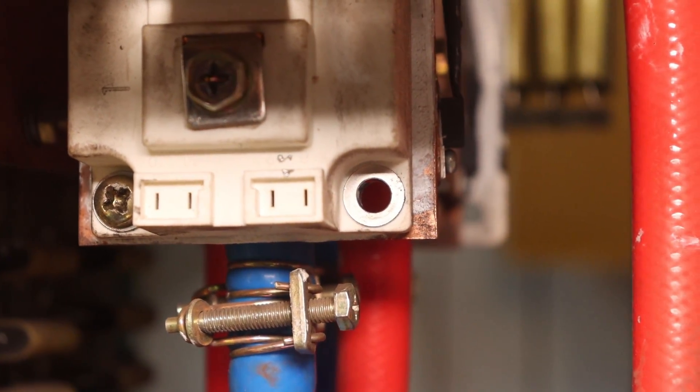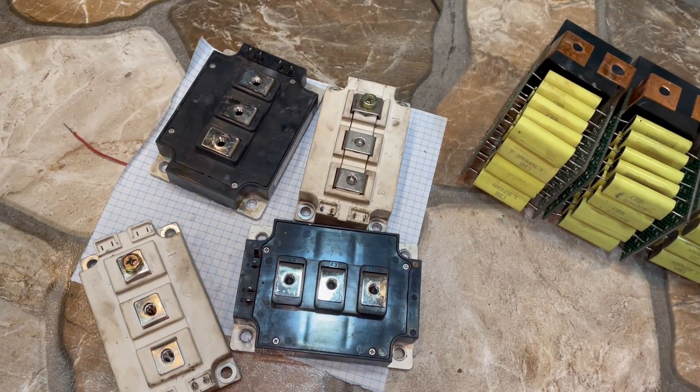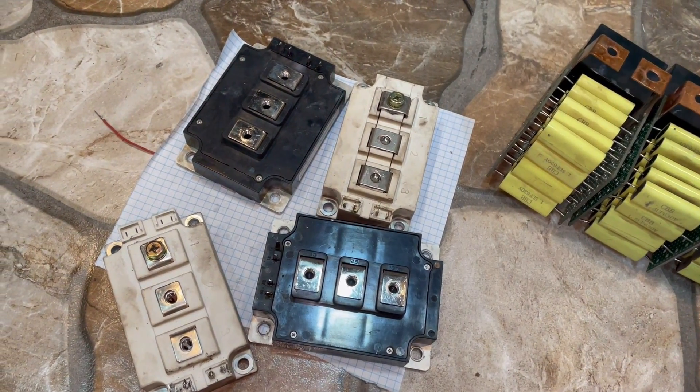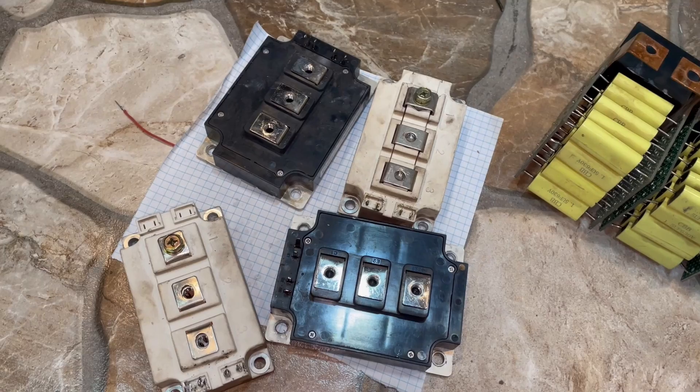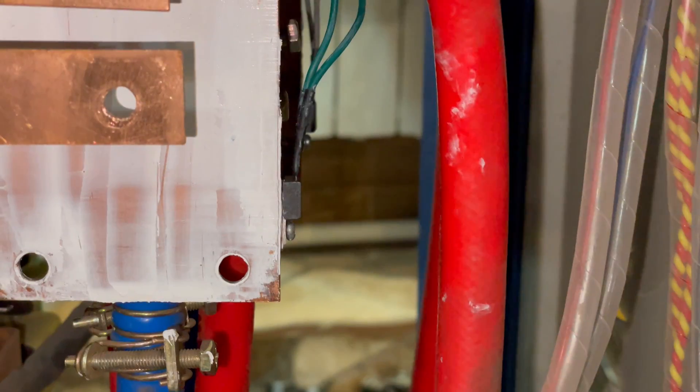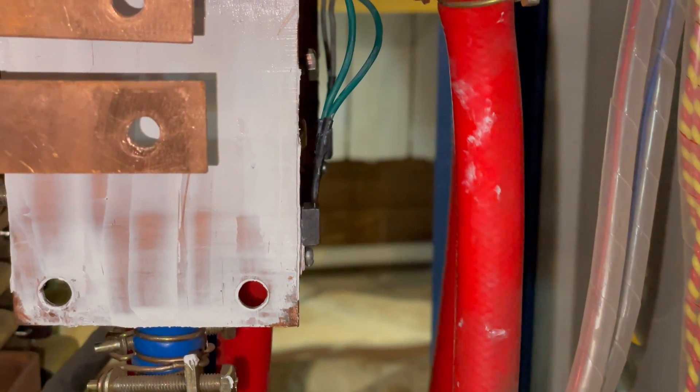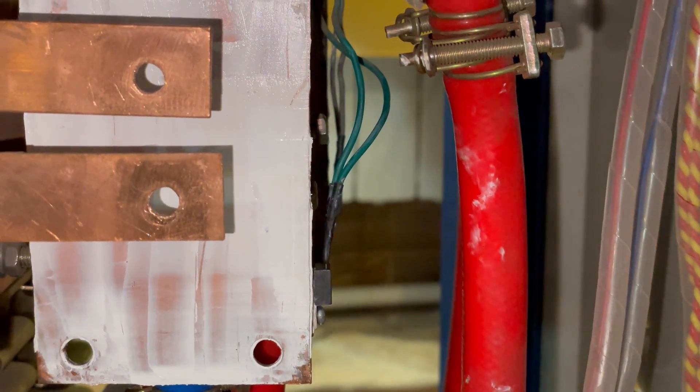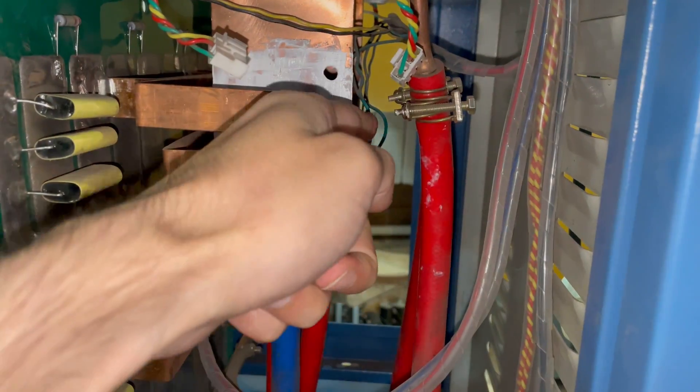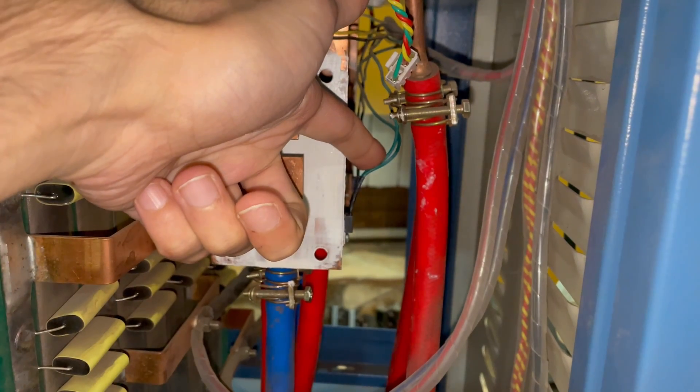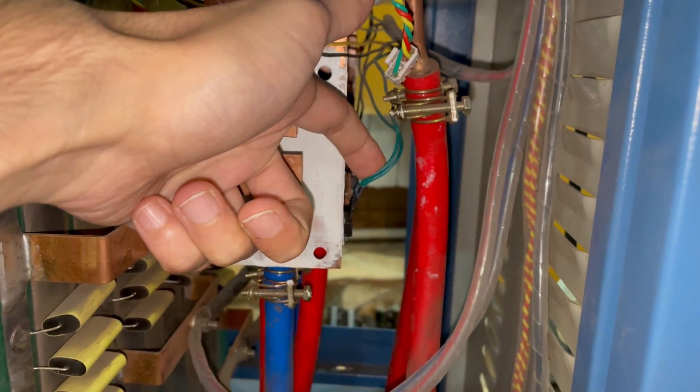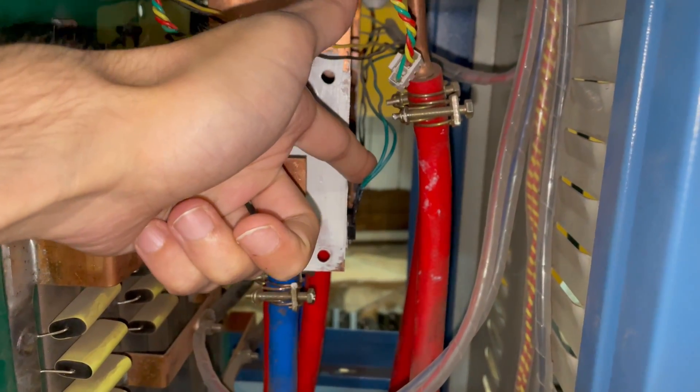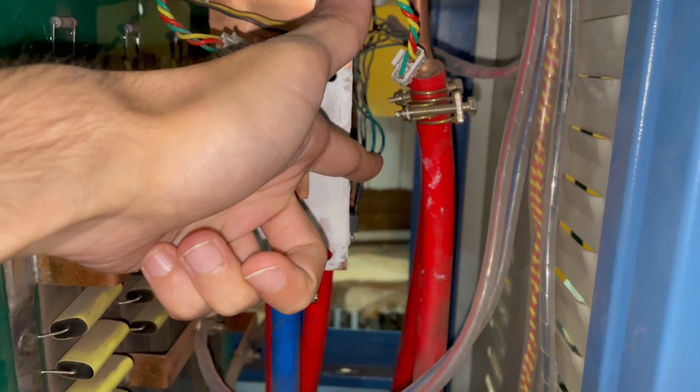Next I took out the IGBT modules. By the way, each module has an individual temperature control in the form of a temperature sensor attached to the water cooling tanks. And I also checked the temperature sensors.